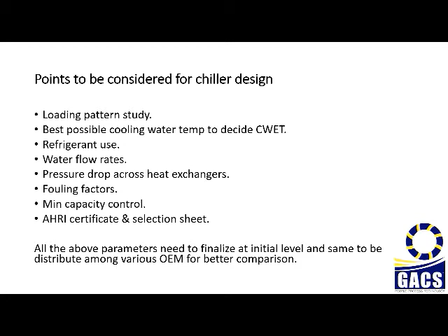Then there is the AHRI certificate and selection sheet. So before buying a chiller, everyone should ask for an AHRI certificate of that particular model, not the series, because generally there are OEMs who get certified for a series, but there are some models which are not certified, but they sell those models in that series range. So we should be very careful with this AHRI certificate, because this AHRI certification will help us gain the trust that this machine is efficient. Whatever is written on the paper is truth, and that will perform at the site. So all the above parameters need to be finalized at the initial level itself, and those parameters should be similar for all the OEMs. Okay, so those OEMs can select the machine based on these common parameters. There should not be any difference.